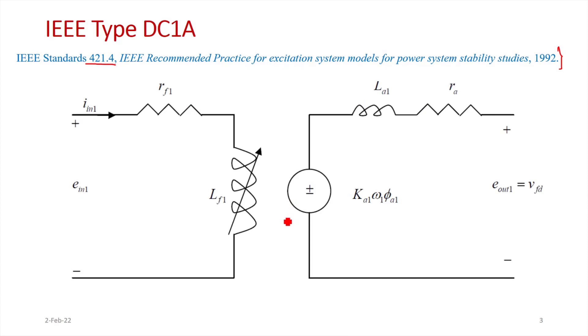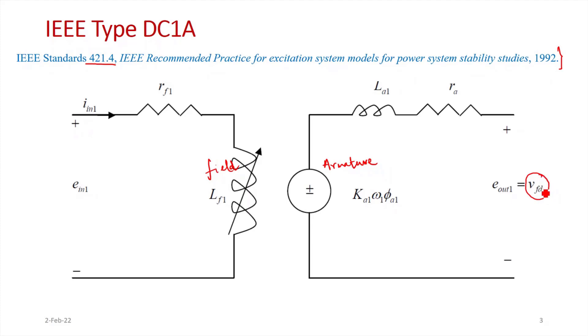A DC exciter may be a self-excited DC generator or a separately excited generator. Here we'll consider a separately excited DC generator. We can see the armature of the DC generator and the field winding. The output voltage produced in the armature circuit is fed to the field winding of the main generator as v_fd. So e_out1, the output of the armature circuit of the DC generator, is equal to v_fd.